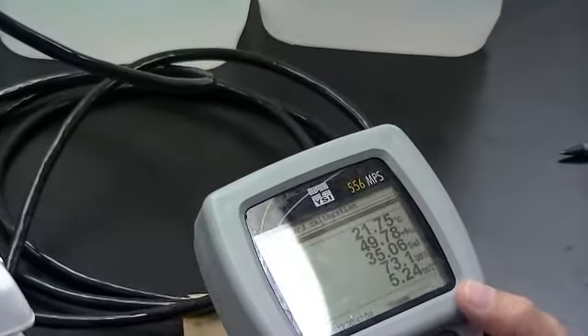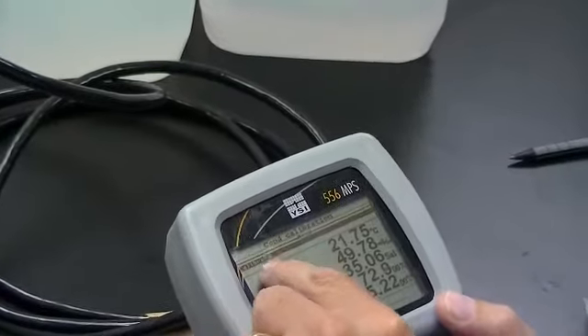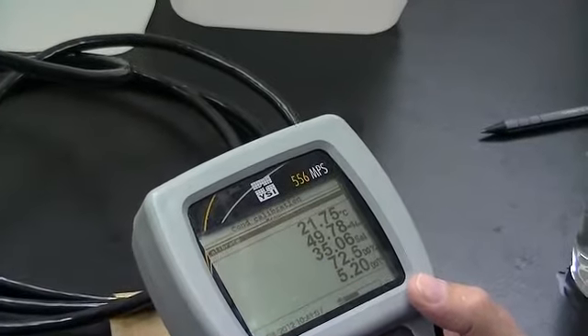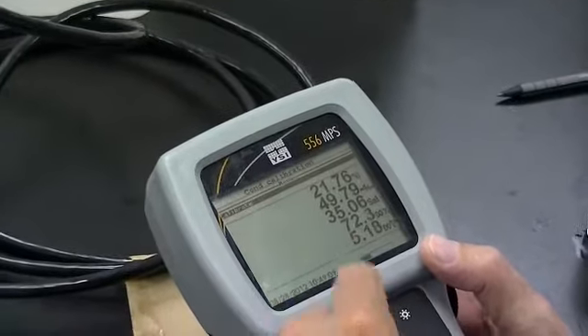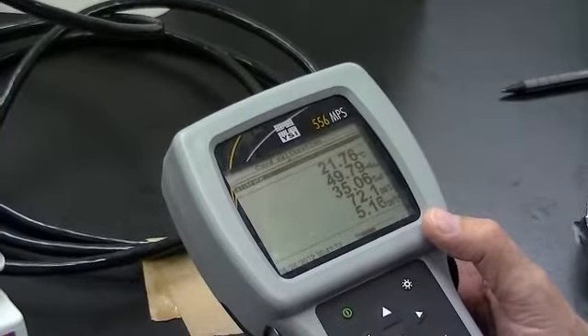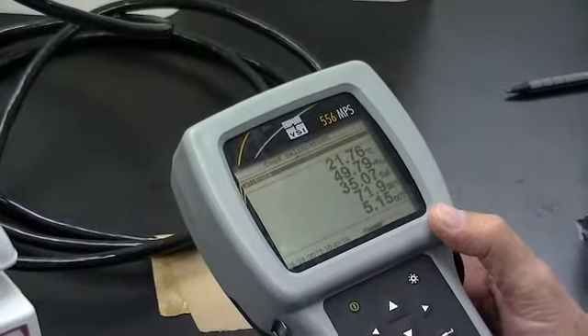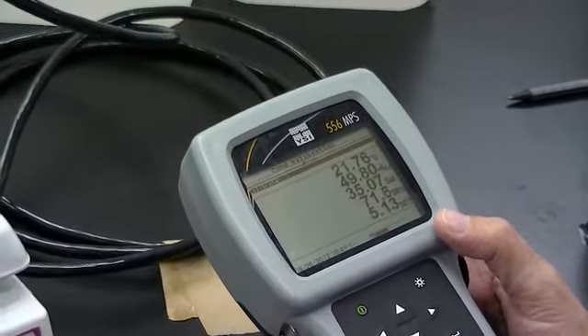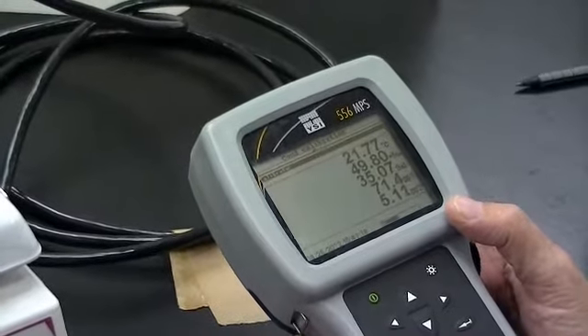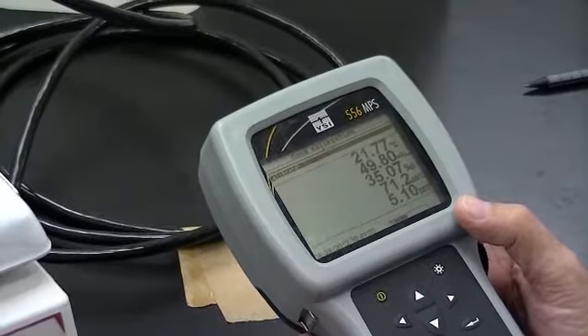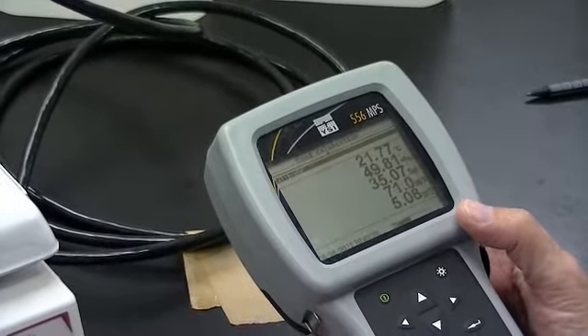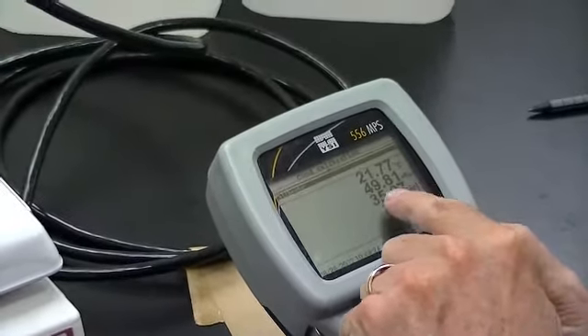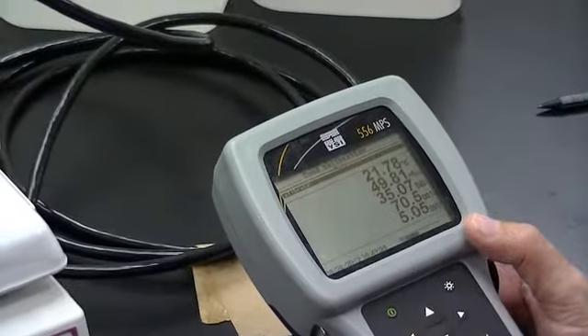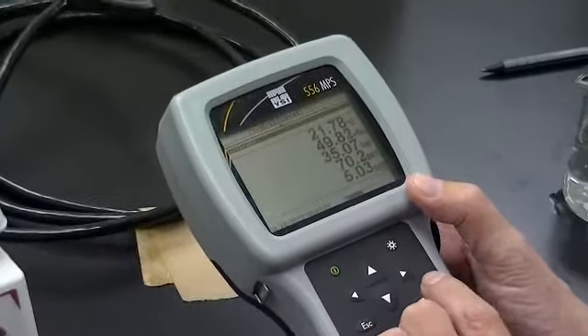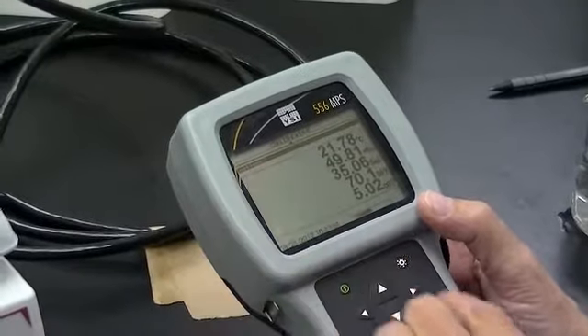And now you're on the calibration screen, and you can barely see right there it says calibrate. Now you basically just watch it until the conductivity and salinity numbers remain stable for a few seconds. I'll just count to 10 maybe. 1, 2, 3, 4, 5, 6, 7, 8, 9, 10. And the salinity didn't change. It says 35.07. Hit return. Now it says continue. Hit return again.